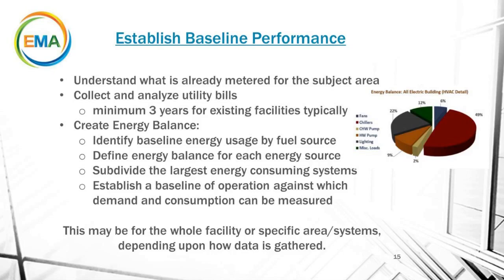Okay, the next question: is the baseline period typically a one-year period prior to retro-commissioning implementation, and do you typically do weather normalization afterward? Good question. Typically we like to look at a 3-year period for existing facilities, because we're seeking a good 18-month window within that where we have quality data. Out of that 18 months, we drill down to find a good 12-month baseline. So we're using 12 months of quality data, and we typically do weather normalize.